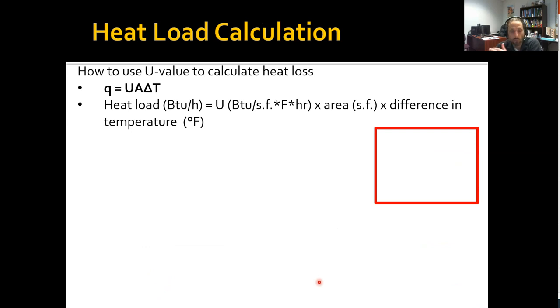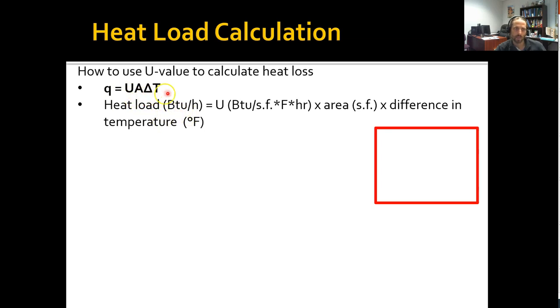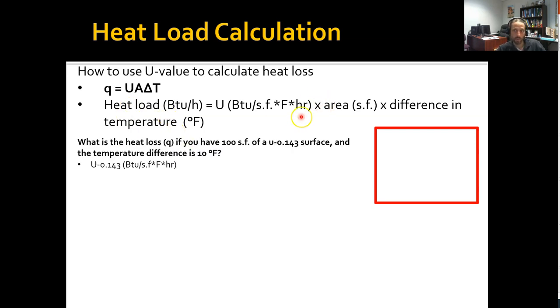Let's go to the actual heat load calculation — this is a really common formula used in the energy industry. Ask just about anyone who deals with buildings and heat loss, and they'll have this equation memorized. The heat load, or heat loss in BTUs per hour, is U × A × ΔT — UA delta T. So the heat load in BTUs per hour equals U times the area in square feet times the temperature difference, delta T. You have to be careful about units: area must be in square feet and delta T must be in degrees Fahrenheit, otherwise the equation doesn't work.